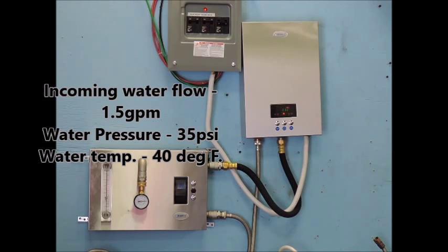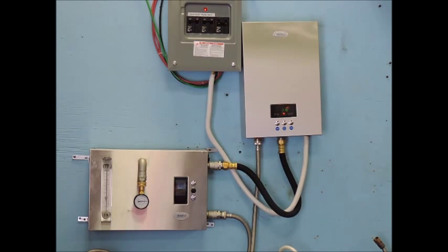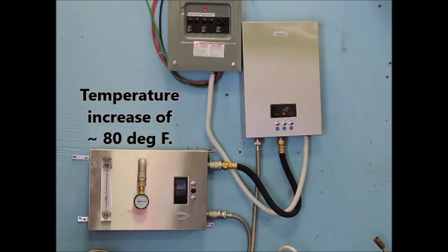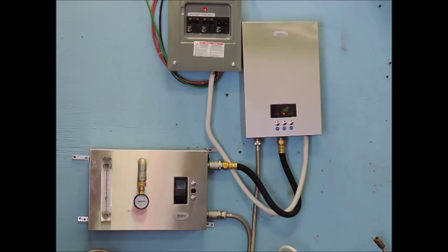Here we drop the flow down even further to 1.5 gallons per minute, still with 35 psi and incoming of 40 degrees Fahrenheit. With this change, we are getting an 80 degree rise, giving us an outgoing water temperature of 120 degrees Fahrenheit.